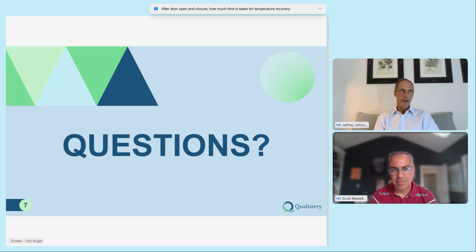I think you'll see published reports in a lot of data sheets that might say 8 minutes, 12 minutes, 22 minutes. But most often those are to get the unit back within the alarm threshold. To actually get it back to its temperature, let's say at -80, it's going to take well over an hour.